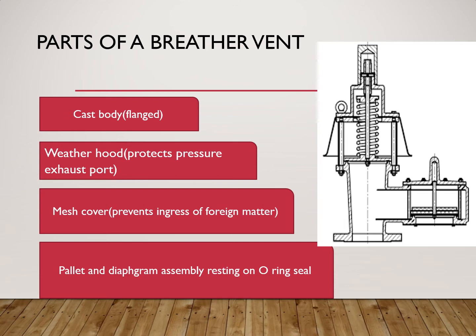Parts of a breather vent. Breather vents have a cast body, which is flanged for connection to the storage tank. The weather hood protects the pressure exhaust port of the storage vessel, since weather conditions may vary from time to time. The mesh cover prevents the entry of foreign matter for the valve vented to the atmosphere or connected to the vent system.